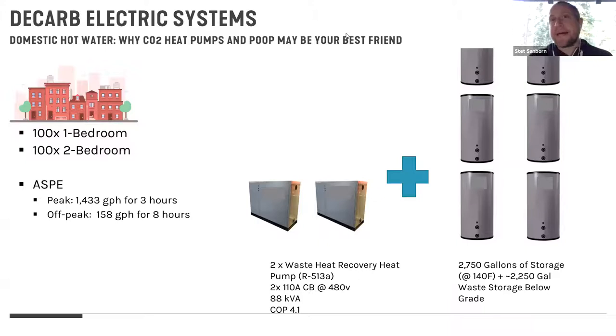But each company has a strategy to deal with the heat exchanger, because that's the biggest risk. You have a lot of biologic material that is looking to grow on something. And so they've taken a lot of the same strategies that wastewater treatment plants have used in their equipment design and just applied it in smaller packaging. But it's definitely something to be concerned with, because if you do get a robust biofilm developed on your heat exchanger, the COP just goes to crap, literally, and the actual energy production goes down as well. As David Eldridge would call this, the sewer thermal HVAC system. Yeah. All right.